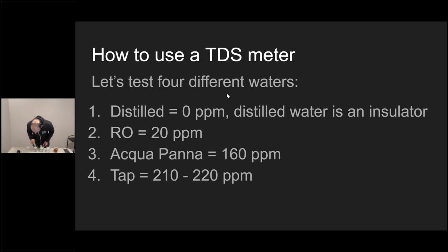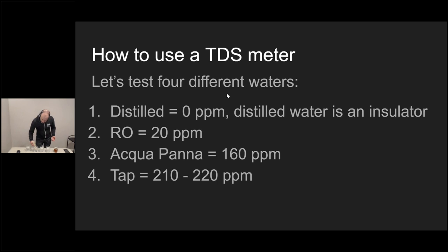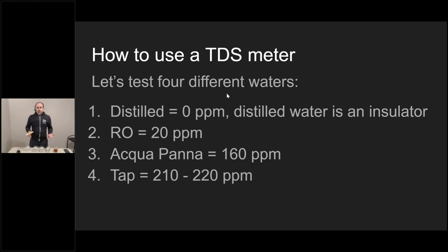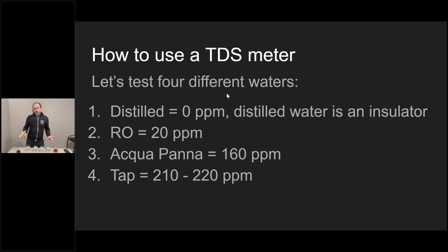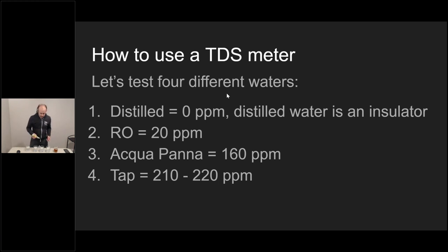Going from my right to my left, we've got five different waters here. The first being distilled water, which gives us a TDS of zero. That's because there are no dissolved solids in it. Water without any dissolved ions is a pure insulator. It doesn't conduct electricity. Second, we have RO, or reverse osmosis water. This is from my own house. I'm getting a TDS of about 20. Most RO systems, commercial RO systems that we use in cafes, will give you a reduction rate of between 95 and 98%.